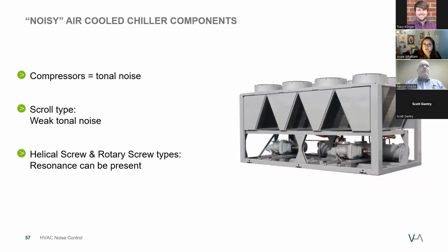But let's talk about the noise sources within an air-cooled chiller, one of those being the compressor. Compressors mostly produce tonal noise. A scroll compressor would produce a weak tonal noise, which is the easiest to address with noise control. However, a helical screw or rotary screw compressor can produce strong tones in the 250 to 2000 hertz octave bands. This can lead to resonance, which requires more intricate noise control measures.